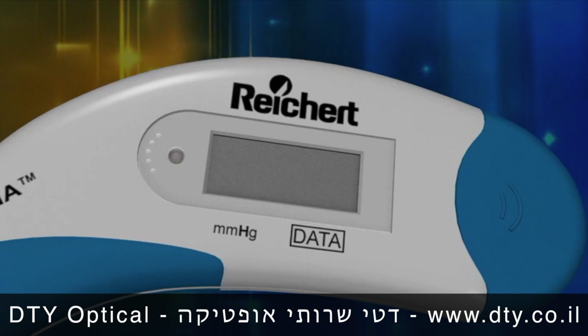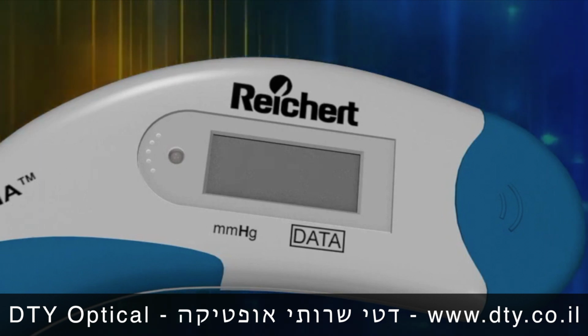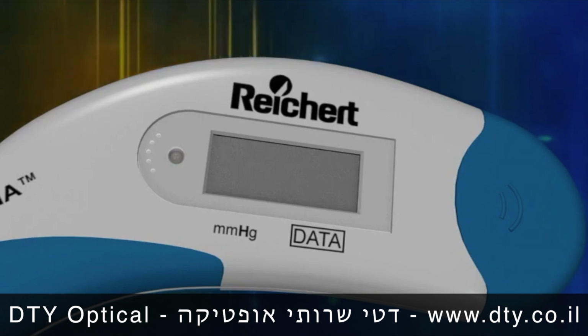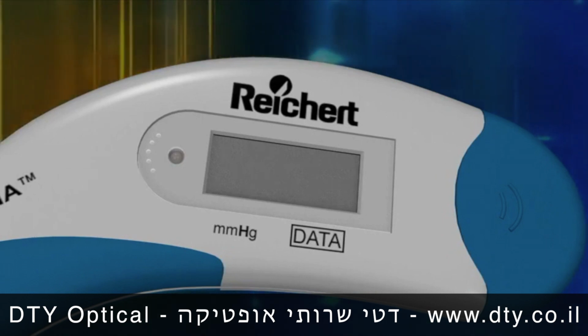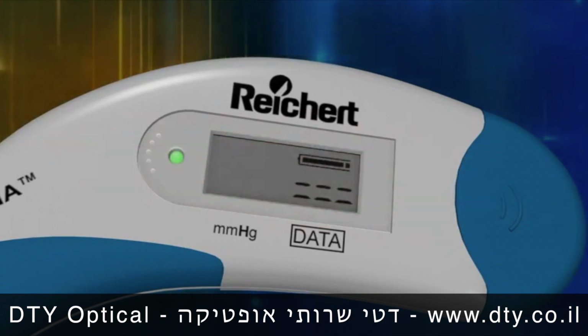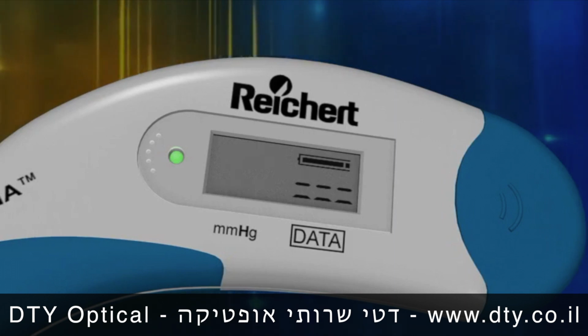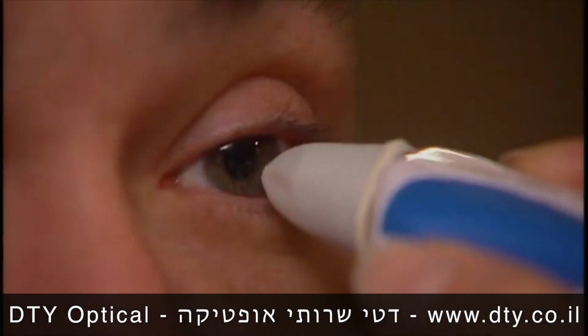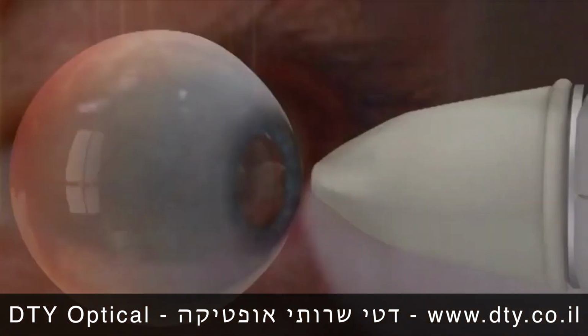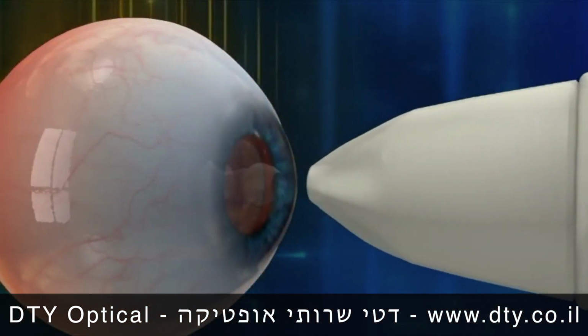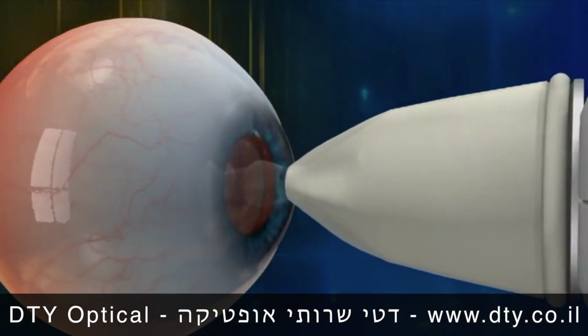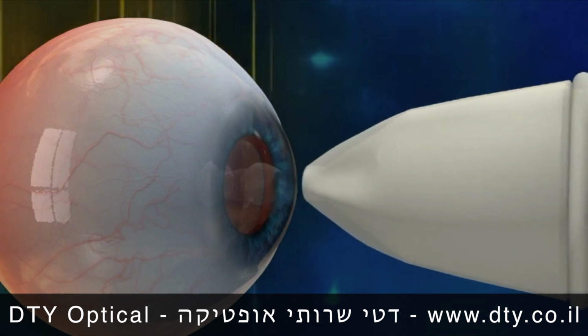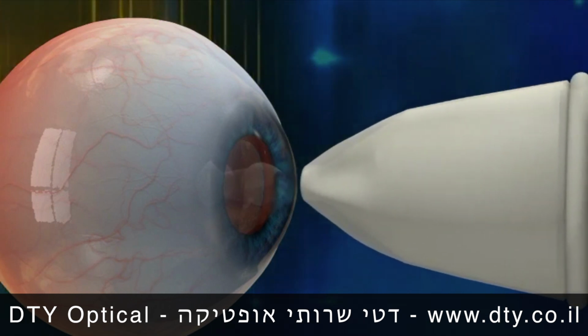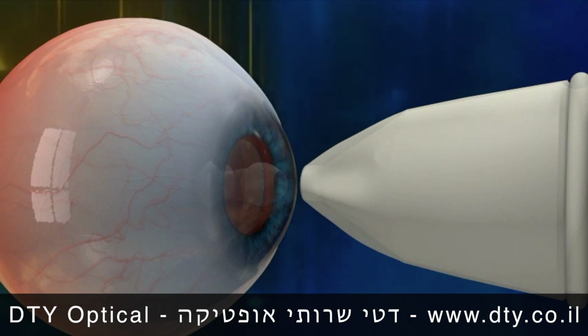To reinitiate the measurement mode, simply press the operating button again one time only. After the double row of dashes is displayed, proceed with the IOP measurement. Gently applanate or tap the transducer on the patient's anesthetized cornea. Notice how the Tono-Pen Avia tonometer is perpendicular to the cornea, and the taps are light, quick touches.